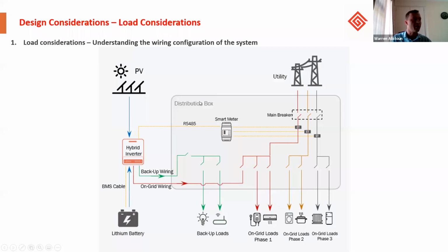So, understanding the wiring and configuration of the system. Here's an example of how a hybrid inverter is connected to a grid. In this example, this is three-phase. For single phase, we just do not have these phases and these CTs. As you can see, the backup loads, the essential loads, are split from the on-grid loads. The inverter speaks Modbus to the smart meter, and the smart meter gathers the data required for the inverter to understand what is being used, what is delivered to the utility, and, very important, for zero exports.